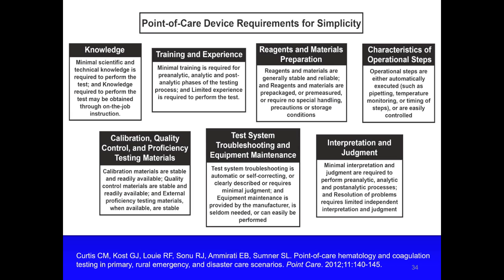And now let's go to slide 34, which shows point-of-care device requirements for simplicity at the top, and then lists what are essentially the CLIA-waived criteria used in this country, the United States, for the approval of these devices.